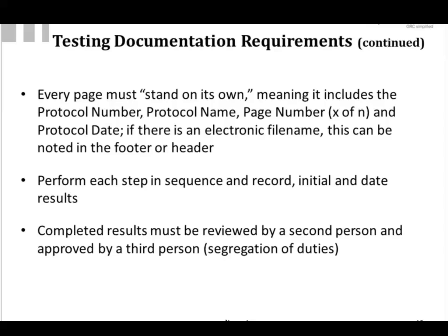You have to perform every step in sequence and record, initial, and date your results. Now, if there's a case where you don't have to do scripts in a certain sequence, if there's some that could be done at different times by different people, you want to divide the whole set of scripts amongst some different resources, that's acceptable, but you should note that as well in your test protocol in terms of your approach.